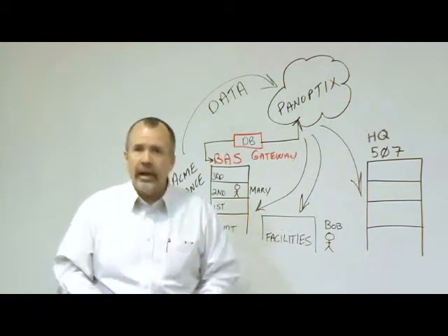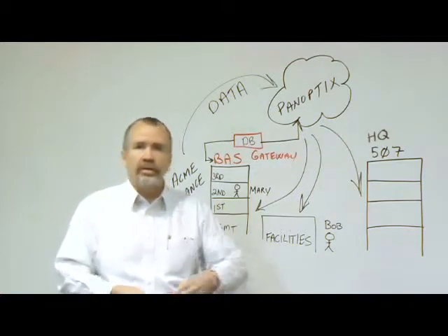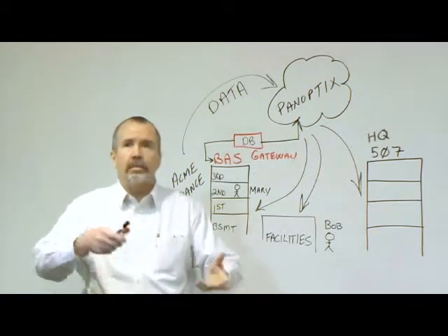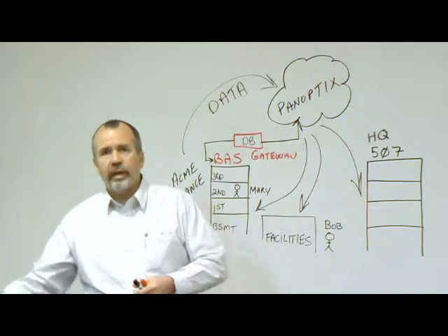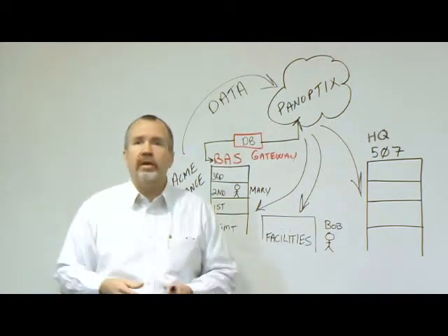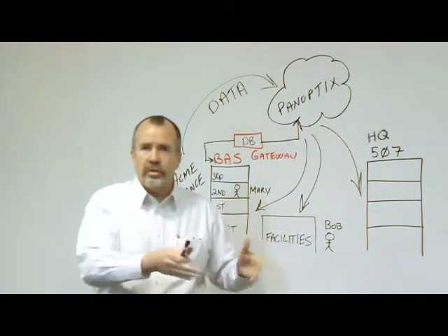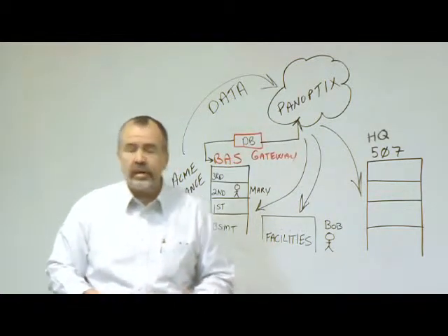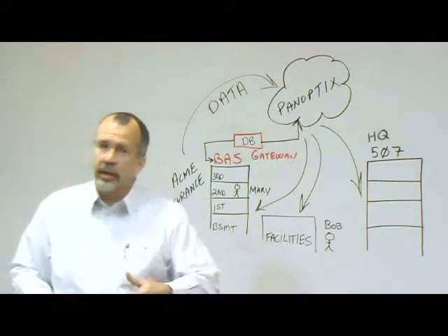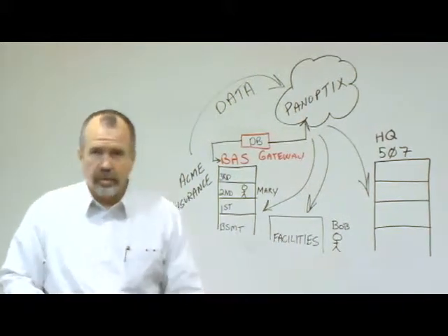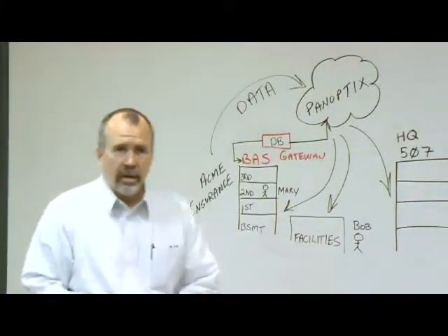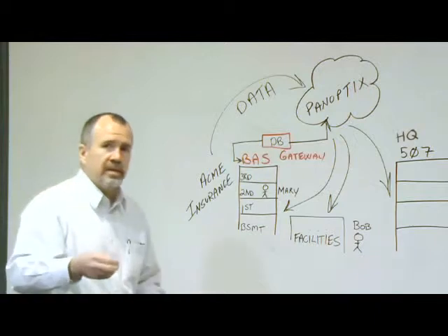Now he takes the ladder back down, puts all his tools together, apologizes to Mary for disturbing her day, puts the ceiling tiles back, crawls back down out the building, and heads off to figure out what the next issue may be to contribute to the heating problem. Typically this is going to be the air handling unit. And from the air handling unit he'll proceed to the chiller. And from the chiller he'll proceed to the tower if the issue seems to be systemic.